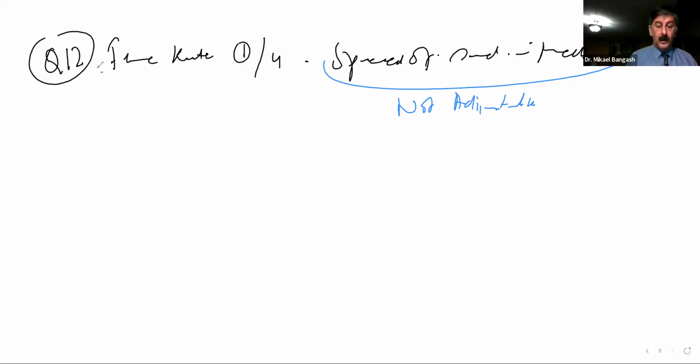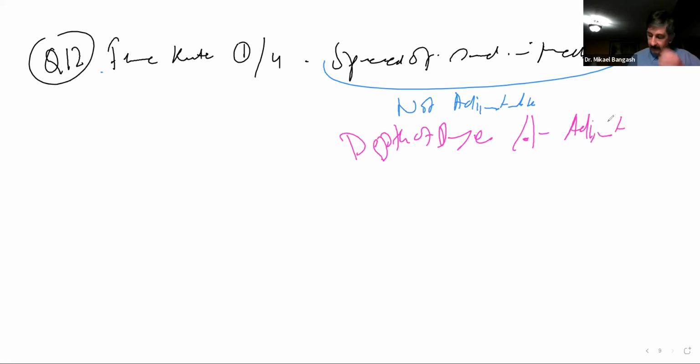But it will still have an effect on your frame rate. Another factor that determines your frame rate was depth of image, which, as we said, was adjustable. But the dynamic range of your receiver?